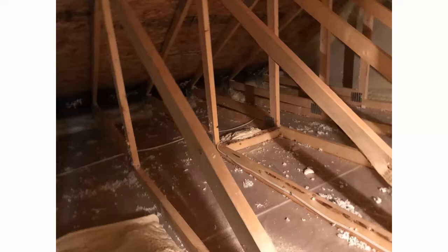You can't really buy a better or best one. There is only one kind. It gets installed in a way that will come off the fan. We'll come up within about 1 or 2 feet of that fan and then back down to the ceiling height. And that's where our condensation collection loop is. And then we head up and out. We try to keep it as short as we can, but we have to allow for that.